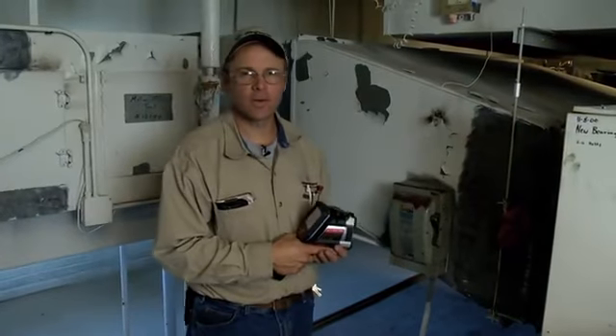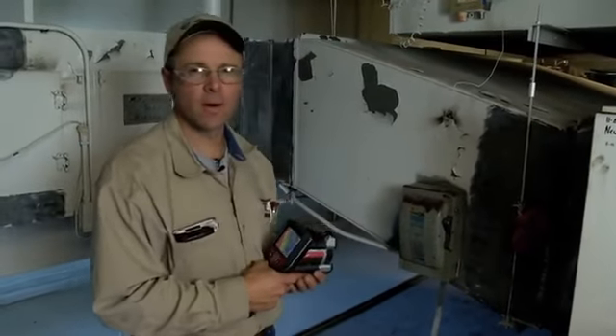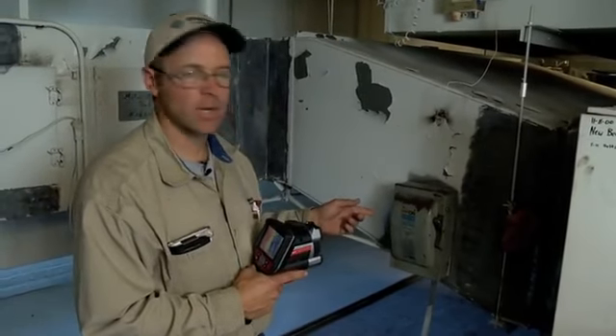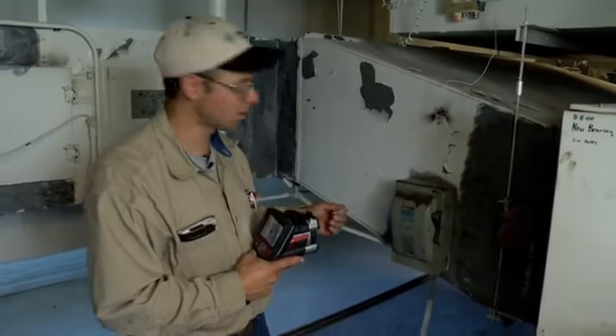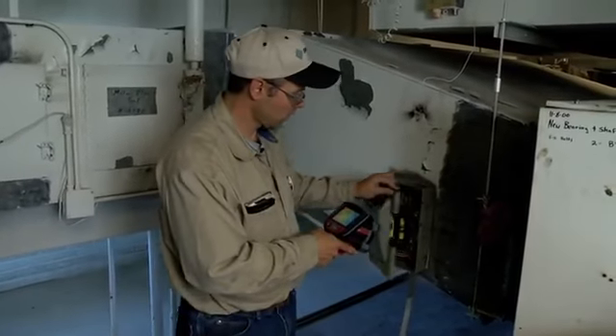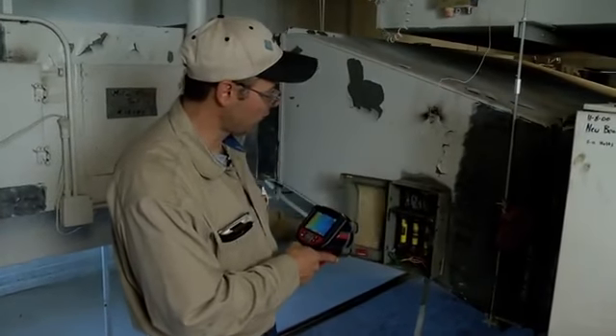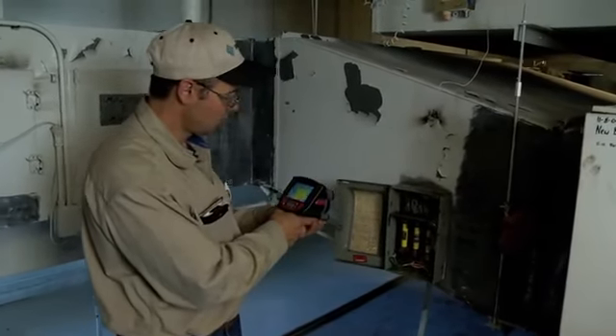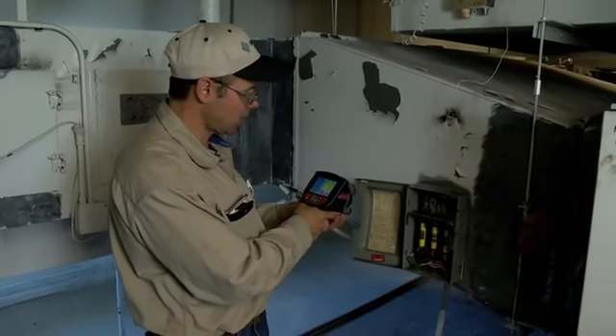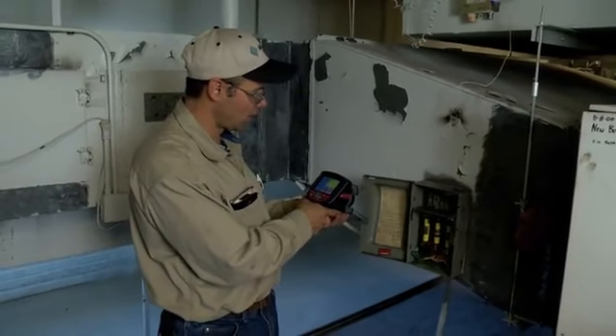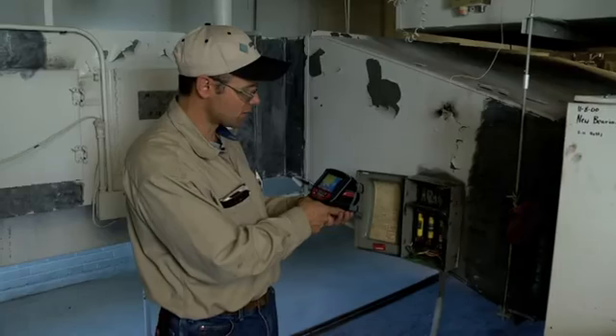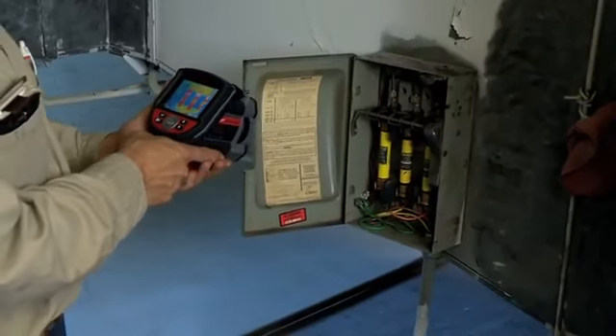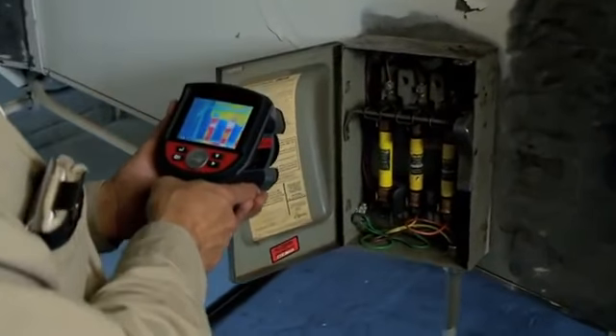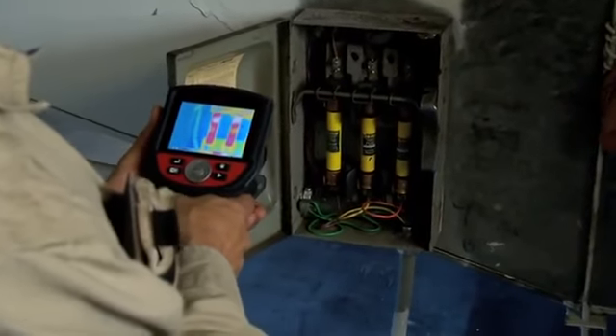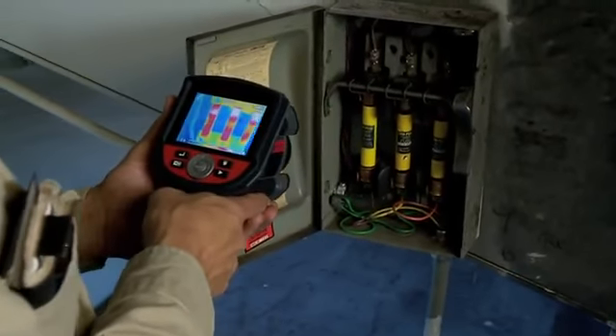Now that I just shut the main off to the air handler, main power, I'm going to check the power wiring on the disconnect, on the fuse disconnect. What we can look for here, if we had loose wiring connections, we would be able to pick up high temperature readings on the wiring or the wiring connections or the fuses. So here I'm taking a thermal image of each individual device. This is one of the best applications of the thermal imaging gun.